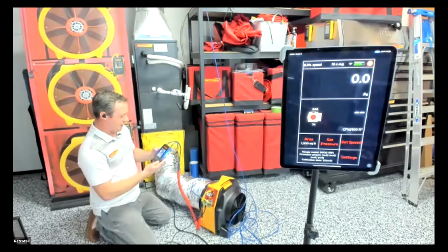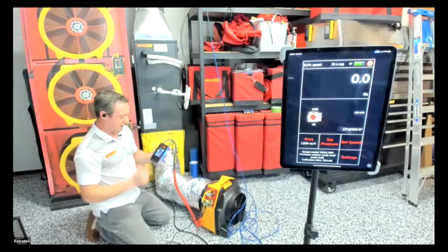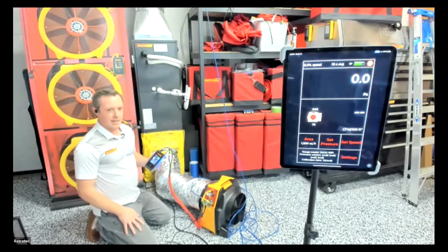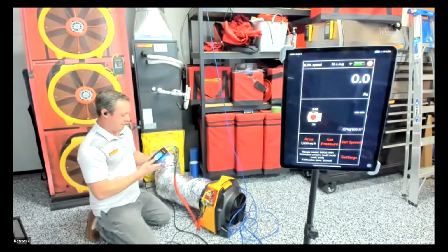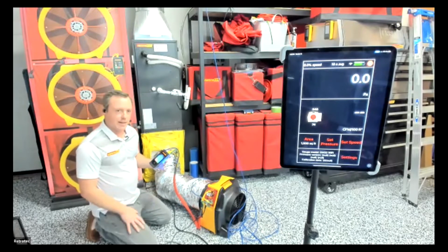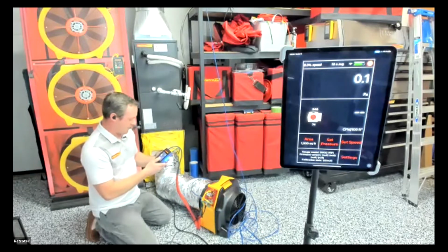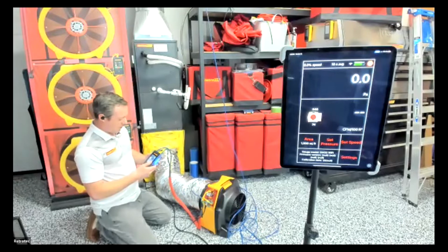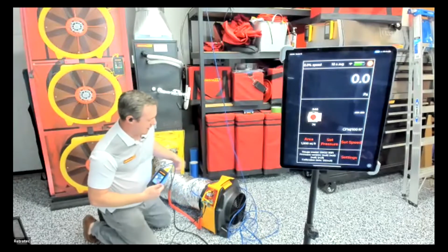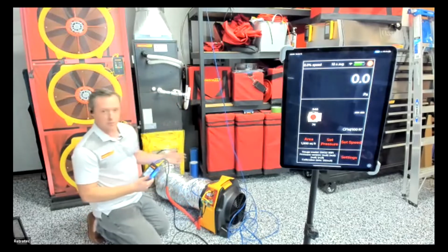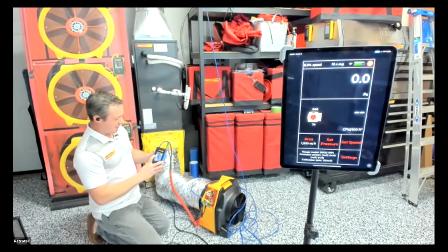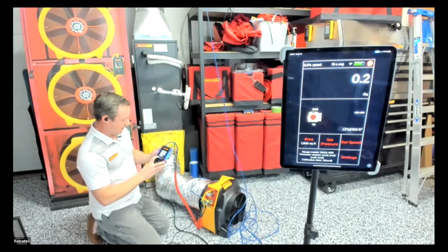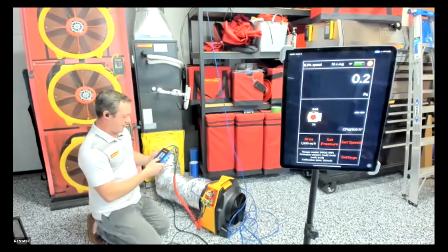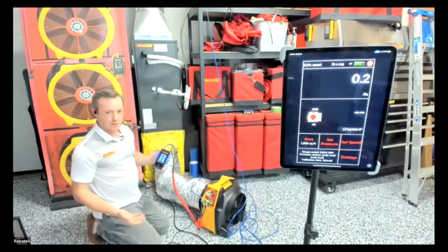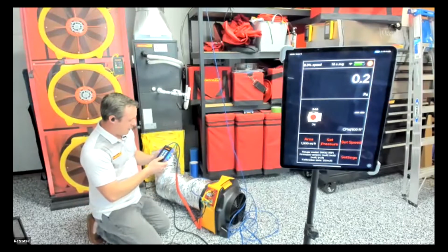And now we see on the gauge here, below the picture of the fan, there's area and 1,000 square feet. If I want to change that, I can just tap area and enter that in. But for this example, we'll keep it at 1,000. So we'll hit cancel. Now we're ready to, aside from the fan setup, again, this is a 340X fan. So we want to make sure we have the right fan selected. And to do that, you tap the picture of it. And if you have the wrong device selected, you just hit change device and it has all of our duct testers there. All competitors' fans are in there too. All of our blower doors are in there.